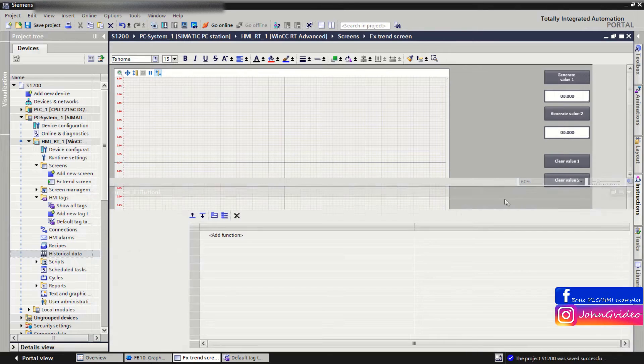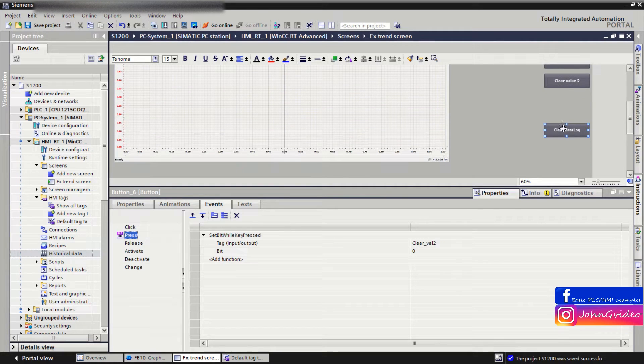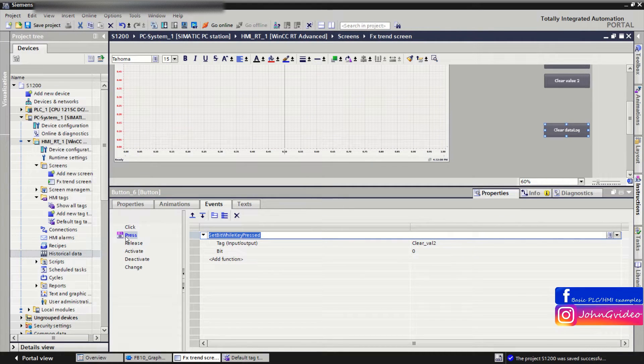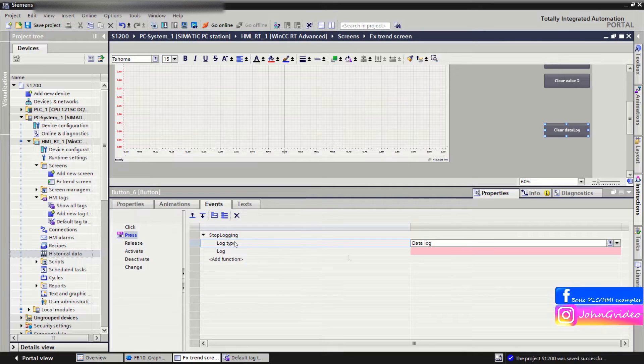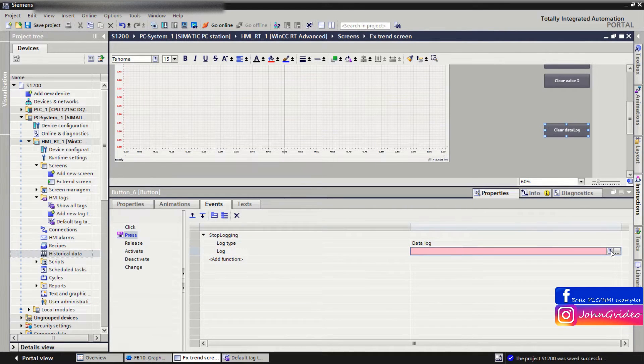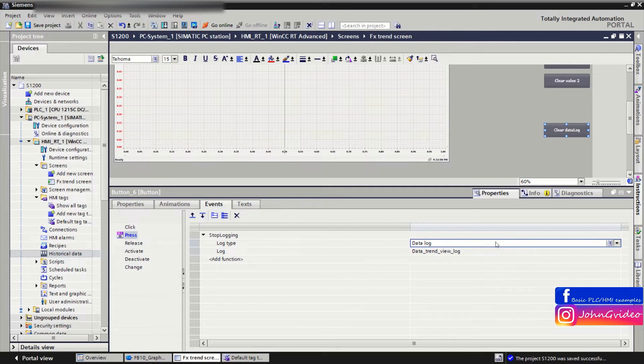Now we go to the events of this button. When we press the button, we stop the data logging of the HMI application. This means in the press action we insert the Stop Logging function. The log type of this function will be Data Log, and as the log we use our log where we are logging this data. Its name is Data Trend View Log.